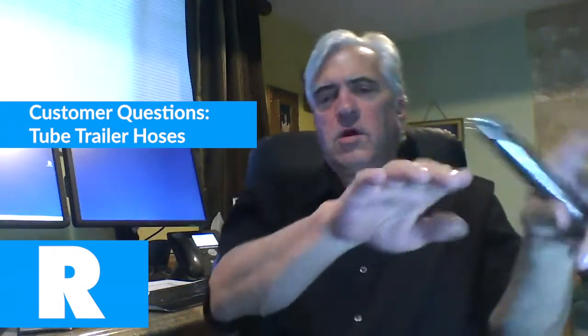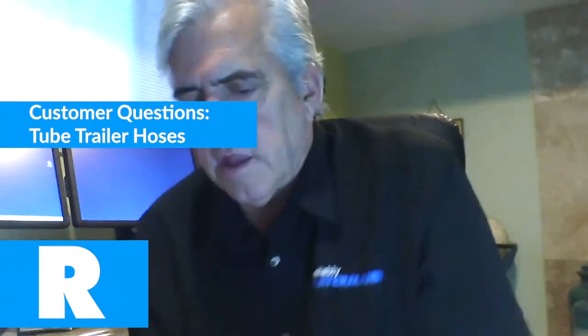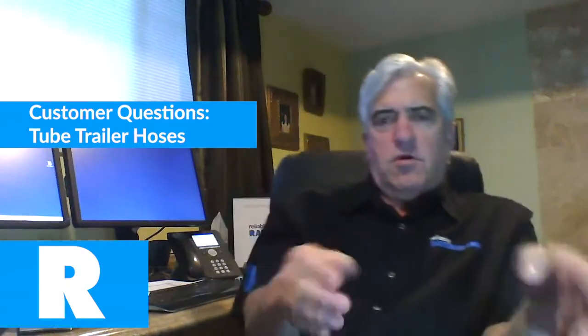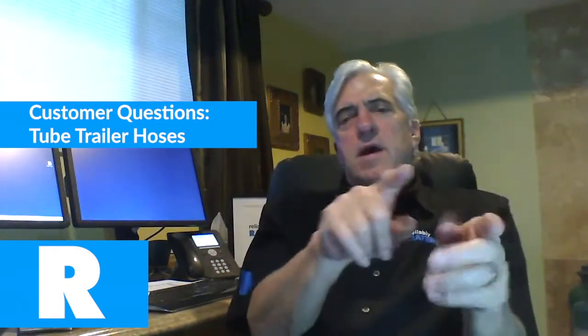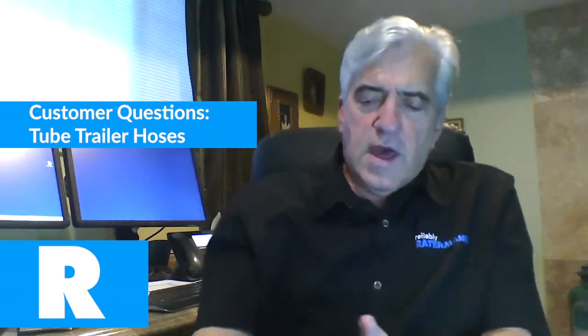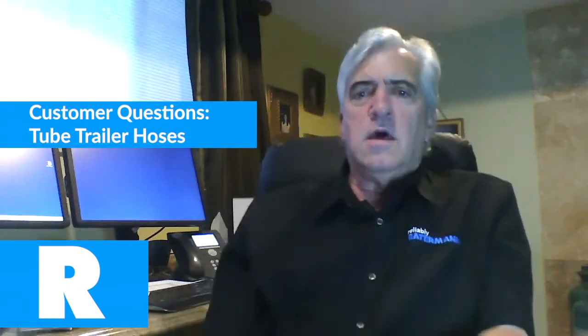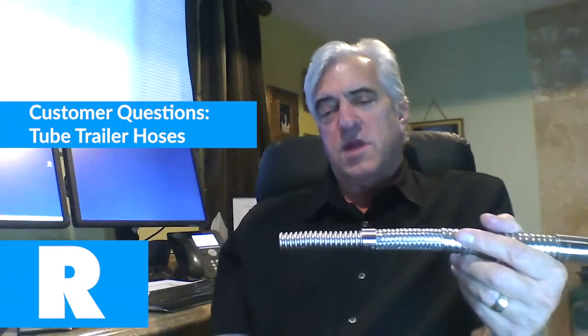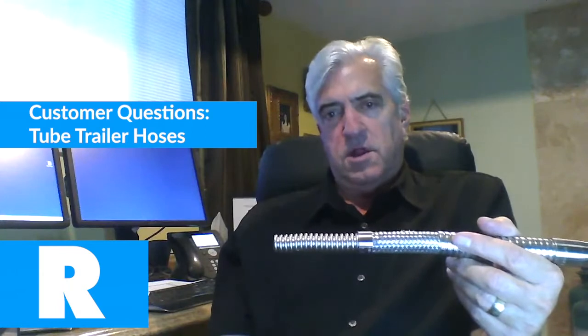And keep in mind, the corrugation is metal that's bent. And so at the very top of that bend, it's very thin. It's probably at its thinnest point. That's where it's going to crack. So it's important that you don't exceed a certain flow rate with standard cryogenic hoses.